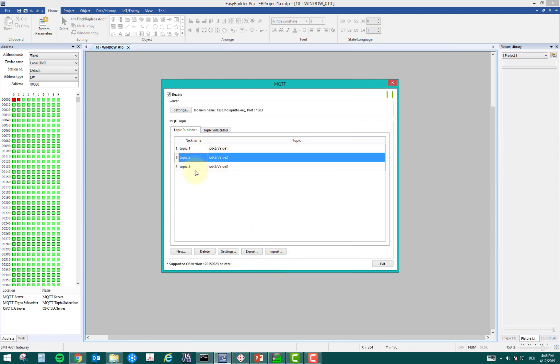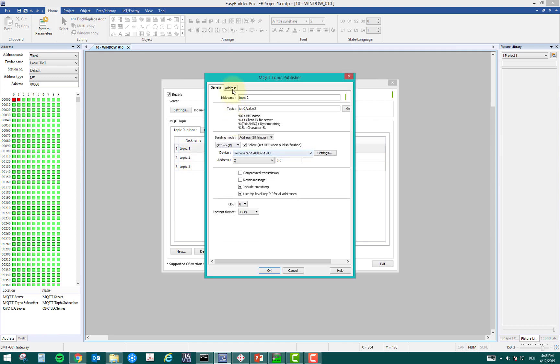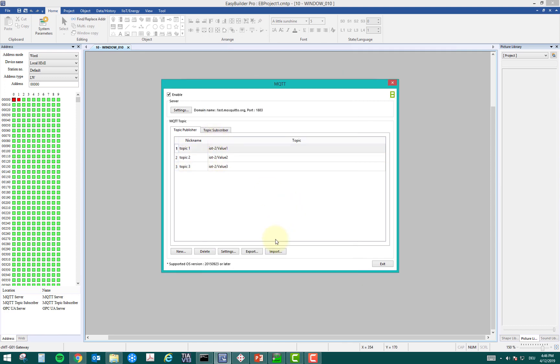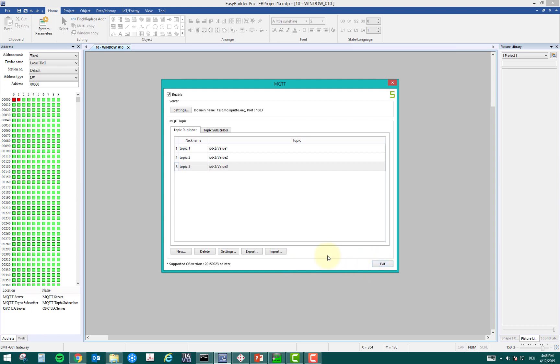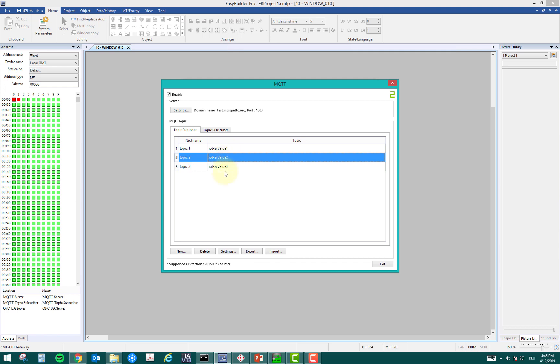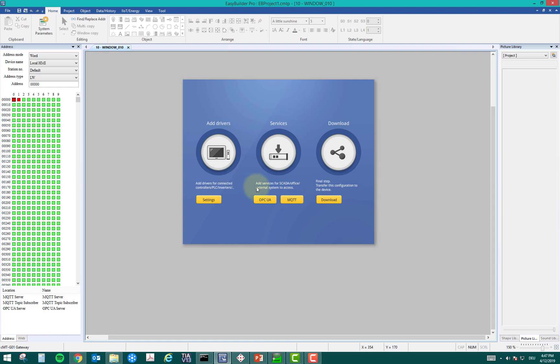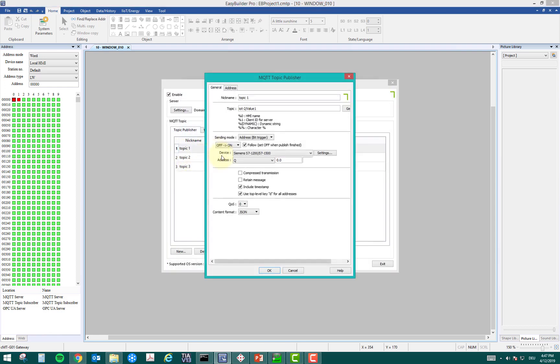So topic1, which is IoT-2/value1, is linked to an OPC tag. I made three topics total: topic2 is linked to value2, and topic3 is linked to value3. In MQTT we always talk in terms of topics to subscribe and publish, so I'm moving three tag values — value1, value2, and value3 — to the MQTT cloud. For the sending mode, I set it based on a bit trigger. When bit q0.0 goes from off to on, it will push the tag value to the cloud.